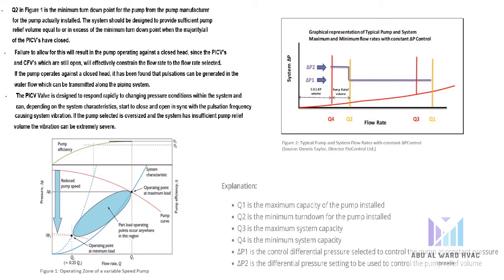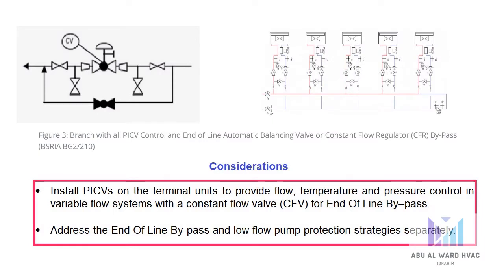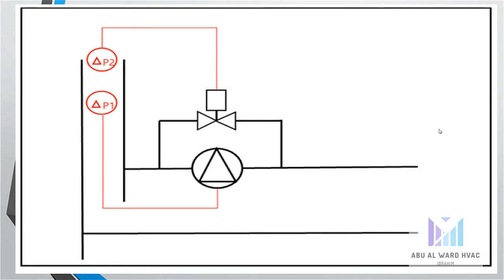Low flow pump protection: install an externally adjustable constant flow valve CFV as an end-of-line bypass valve on each branch of terminal units to avoid dead legs. Circulate chemicals and ensure good temperature response. Considerations: install PICVs on the terminal unit to provide flow temperature and pressure control in variable flow systems with a constant flow valve CFV for end-of-line bypass. Address the end-of-line bypass and low-flow pump protection strategies separately. And this is the schematic for this case.